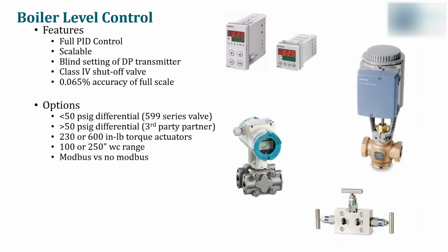Options include, if it's less than the 50-pound differential, you can use the 599 series valve. If it's greater than the 50-pound differential, we do have a third-party partner that we work with that has valves that are good up to 150-pound differential. They offer two types of actuators, either 230-inch pound or a 600-inch pound actuator. The range on the DP transducers is either 0 to 100 inches or 0 to 250 inches. And you either have the ability for Modbus or no Modbus capability on the RWF. In terms of sizing, we do have a feed water builder program, and we're going to do an example right now.